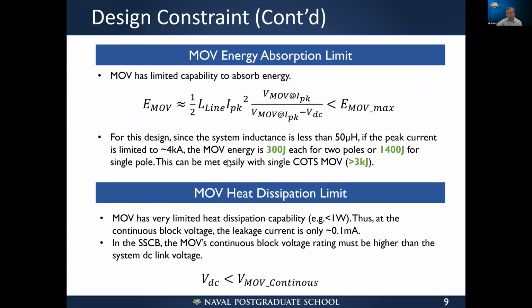Luckily for this design, since the system inductance is less than 50 microhenry, if the peak current is limited to about 4 kiloamp, and I will show how we do it, then the MOV energy is only 300 joule each for 2 poles, if both of them can work together, or about 1400 joule for a single pole. This is the worst case. This can be met easily with single commercial off-the-shelf MOVs, typically higher than 3 kilojoule.